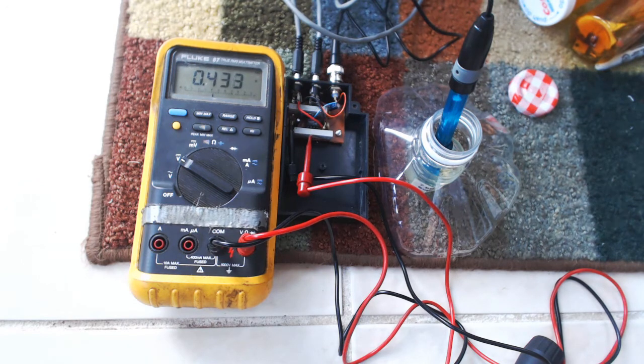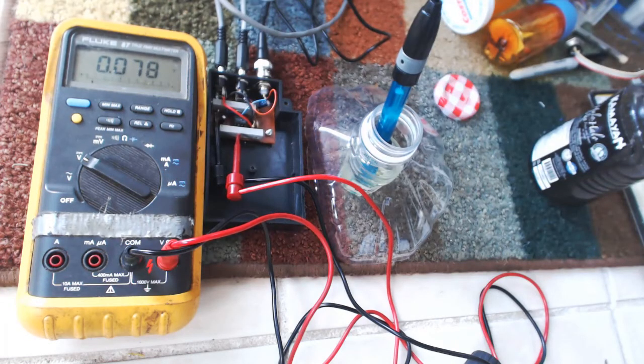And I went ahead and turned the meter on, turned the power on. As you can see, the voltage is declining. It should be as close to 0 as possible. So I'm going to walk away for about 30 minutes and come back on this one. I've learned the probe isn't particularly stable, especially on 7 pH. So in this case, I'm going to say 0.07, 0.08 is close enough. I found out it does tend to oscillate a little bit on the bottom end like this.